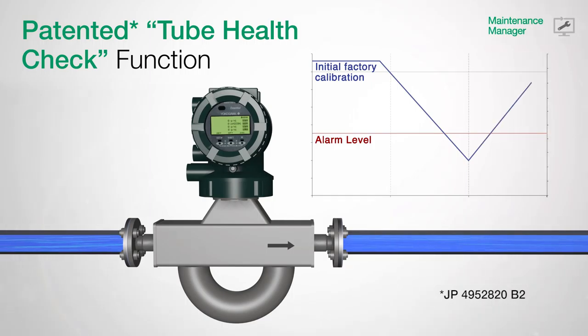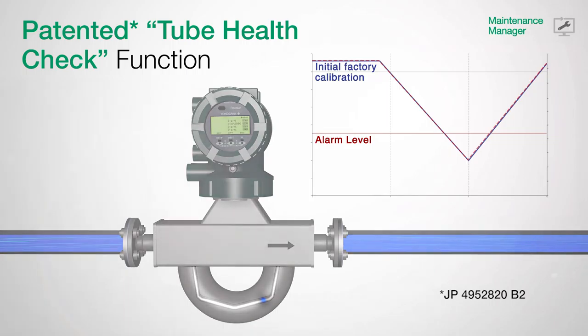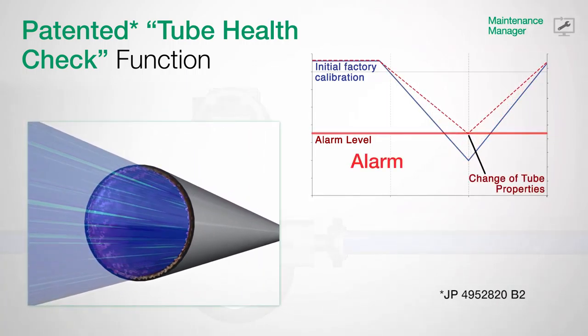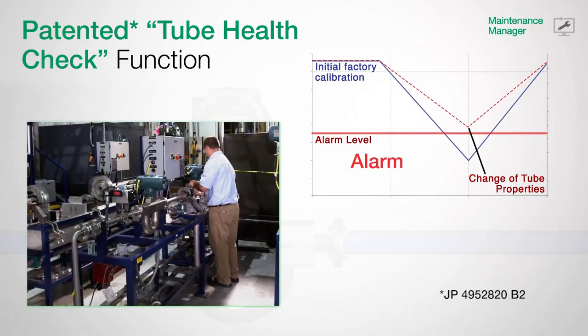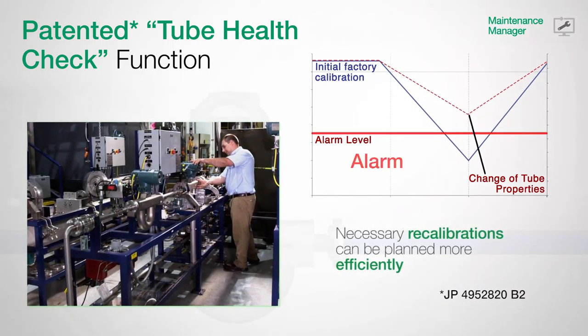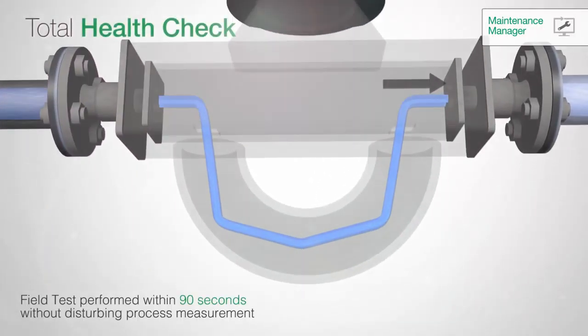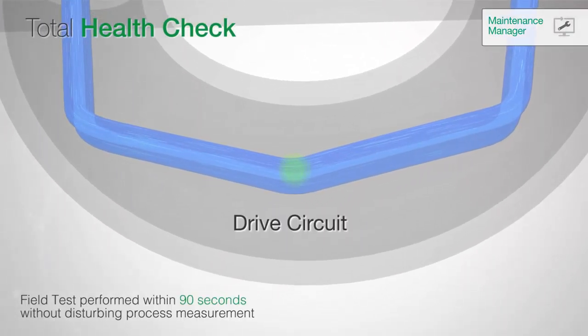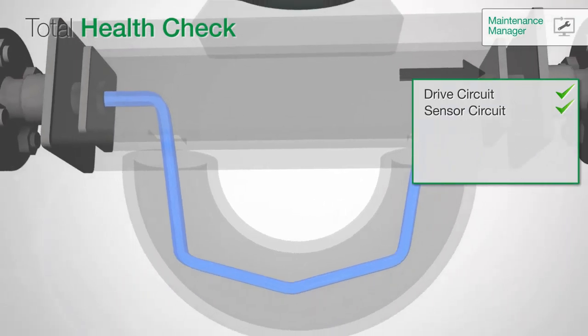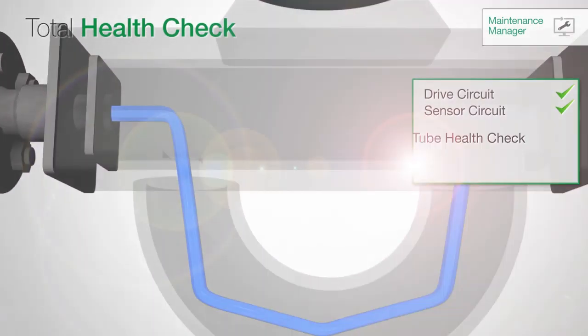But with the newly developed and patented Total Health Check, a calibration check of an installed Rotamass can be performed while in operation without disturbing running measurements. Influences on the meter are diagnosed at an early stage, thus eliminating downtime and reducing your costs. Any necessary recalibrations can then be planned more efficiently.